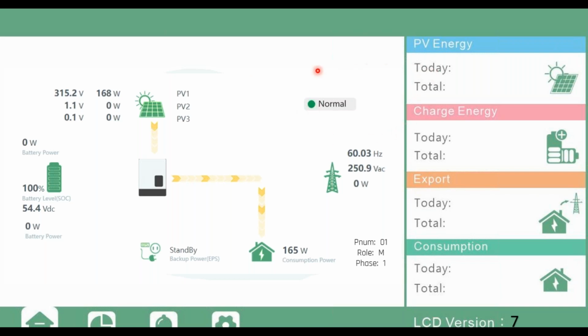Initially, when booting up the system using batteries, you might get a warning indicator, but that just means, by default, you will see the inverter trying to search for grid, right? And your grid is not enabled yet because we're doing the first initial phase of commissioning. So you might get a warning that says trip by AC or AC abnormal. It's perfectly normal. It just means that it's not recognizing AC.